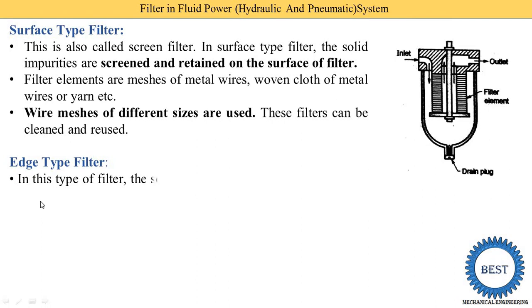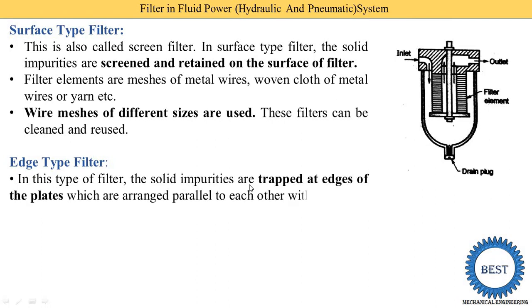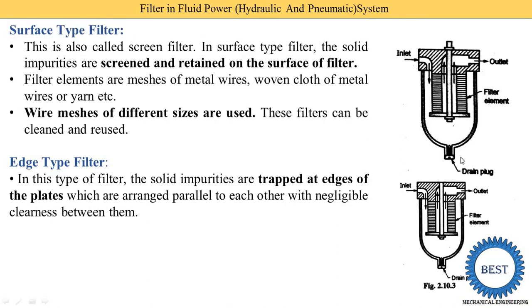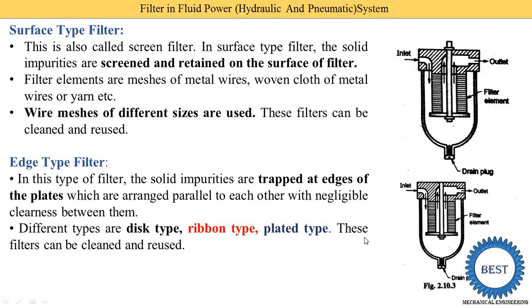The next one is the edge type filter. In this type of filter, solid impurities are trapped at the edges of plates arranged parallel to each other with negligible clearance between them. Rather than metal wire mesh like the surface type, here plates are used. Impurities are collected at the edges of the plates — that is why it is called an edge type filter. As a filter element, options include disc type, ribbon type, or plate type, and these filters can be cleaned and reused.